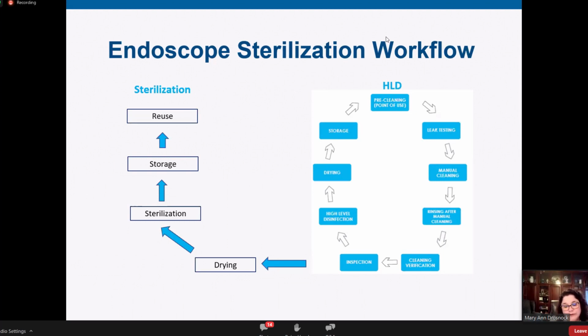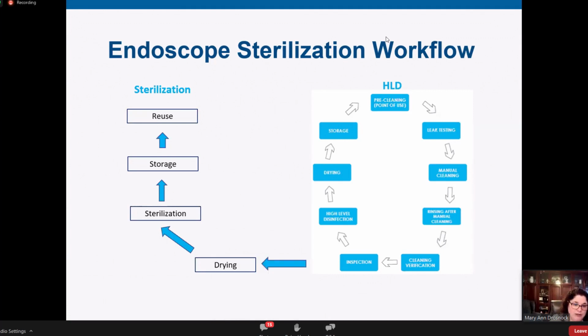And what's great about moving to sterilization is you have a wrapped, storable item that can stay flat in its wrap per your healthcare facility policy on sterilized items. So whatever you have for everything else is what you can do with these sterilized endoscopes. And then we go back to reuse from there. So we see clearly by the IFUs, high-level disinfection is not included as part of the sterilization process.